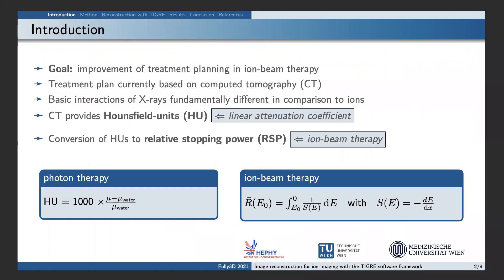Currently, a treatment plan is based on conventional CT, which provides Hounsfield units that are based on a linear attenuation coefficient of the material. Ion beam therapy is based on the stopping power of the material, which describes the energy loss of an ion per unit path length. The stopping power is usually expressed relative to water, referred to as relative stopping power. While conversion from Hounsfield units to relative stopping power leads to range uncertainties in the treatment plan, ion CT allows to directly measure the requested quantity.